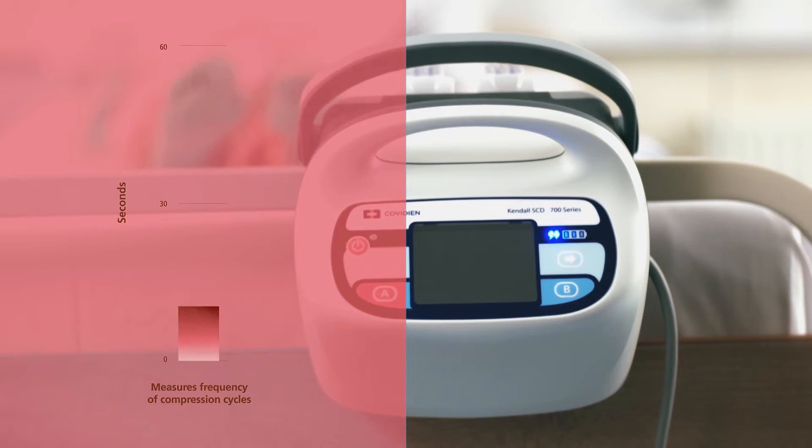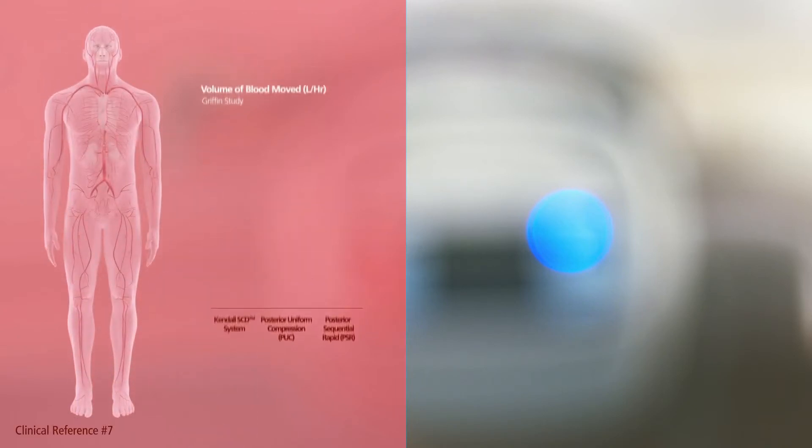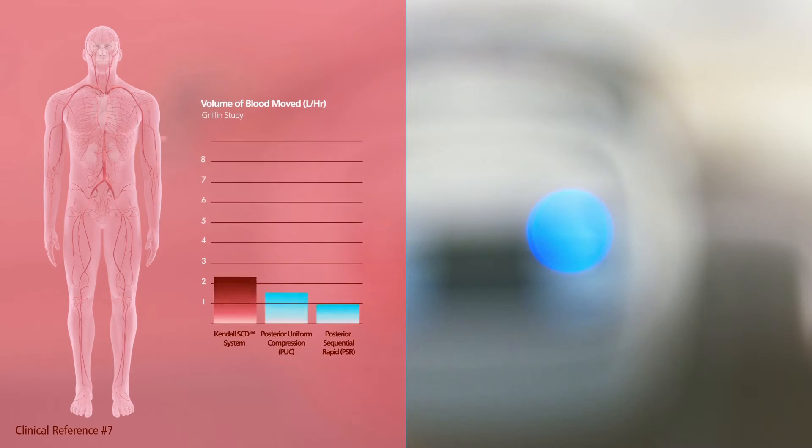VRD works by measuring the time it takes for a patient's veins to refill with blood after being compressed, and then setting the frequency of compression cycles based on the patient's particular venous refill time — anywhere between 20 and 60 seconds. This number is automatically recalculated every 30 minutes.